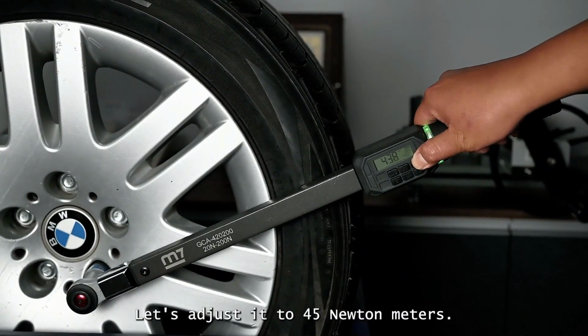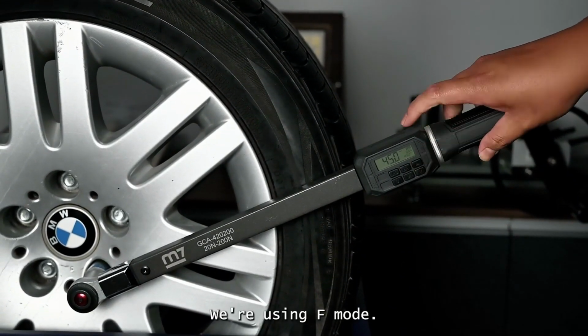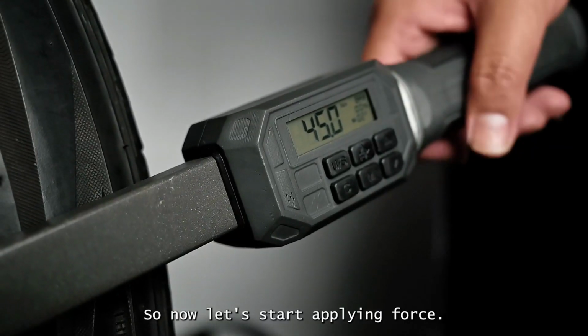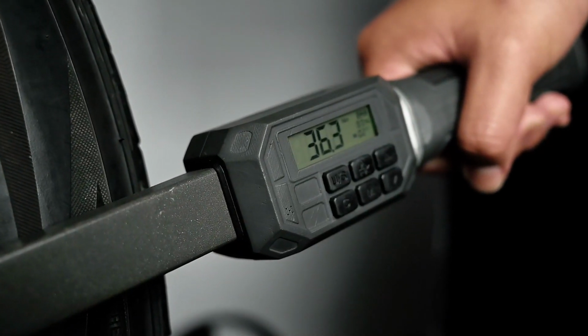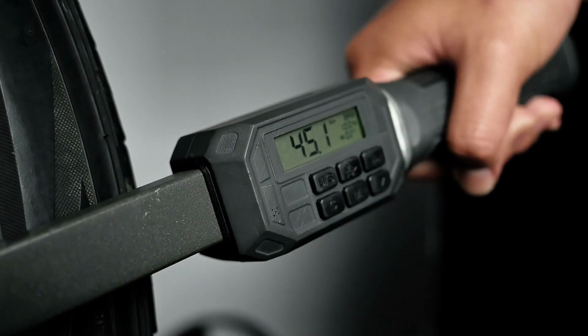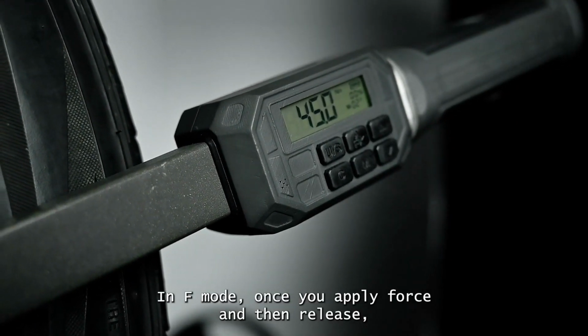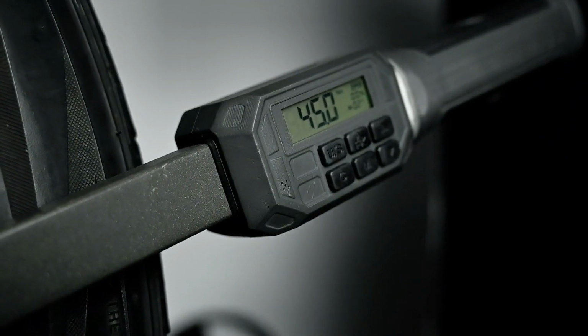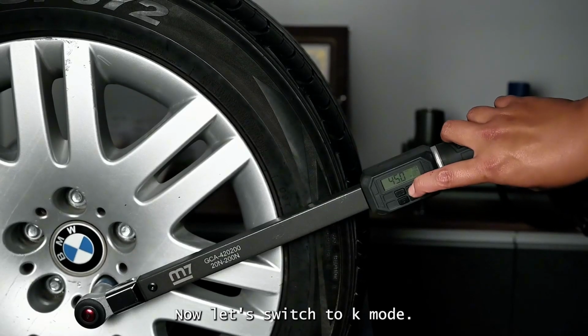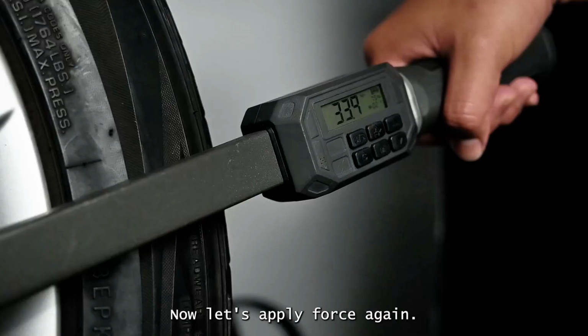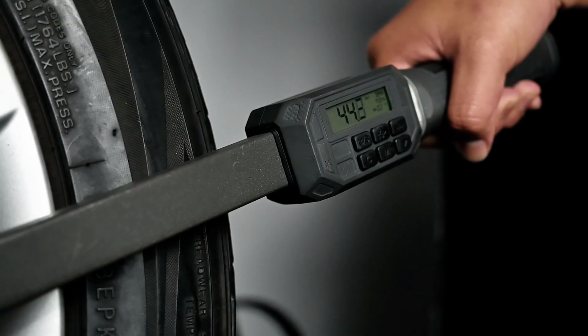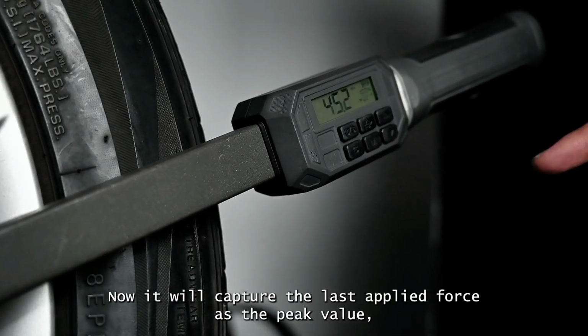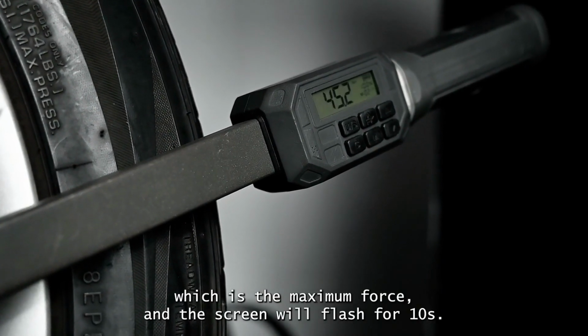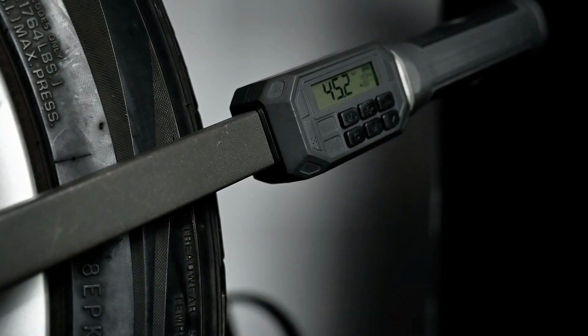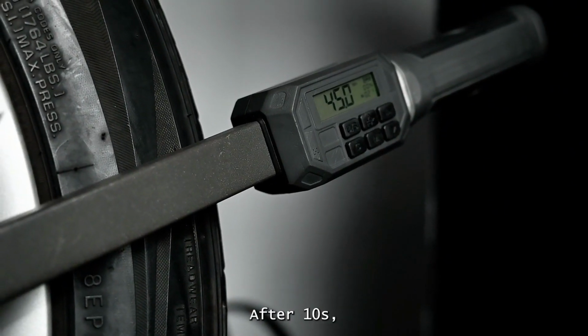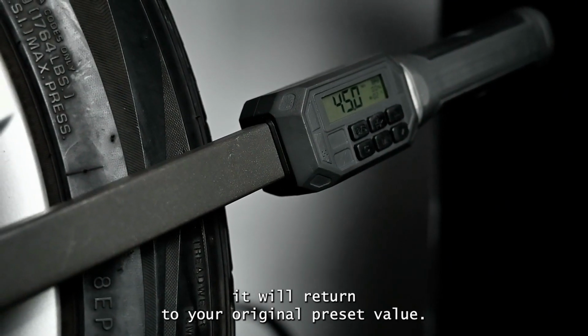Let's adjust it to 45 Newton meters. We're using F mode, so now let's start applying force. In F mode, once you apply force and then release, it will return to the original preset value. Now let's switch to K mode. Now let's apply force again. Now it will capture the last applied force as the peak value, which is the maximum force, and the screen will flash for 10 seconds. After 10 seconds, it will return to your original preset value.